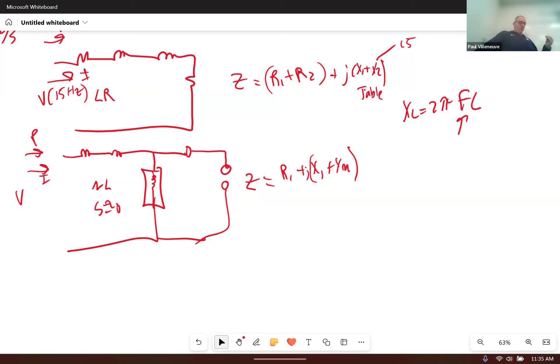Okay. So that's where you would need to adjust for the frequency, because you want to run locked rotor at low frequencies. In the lab, we didn't have the ability. We don't have a 15 hertz power supply. So we're stuck with running it at really high values, and that means we're killing those motors.